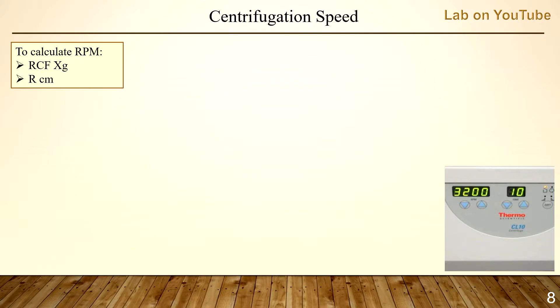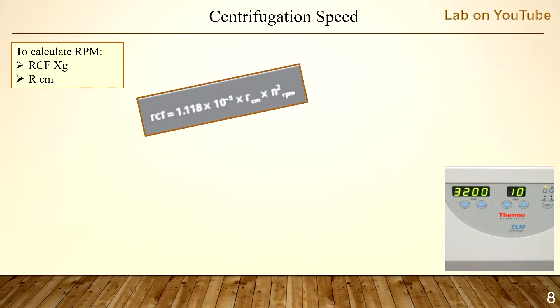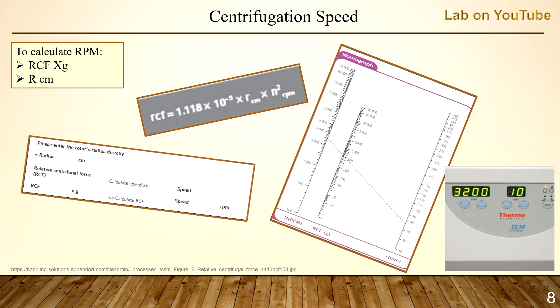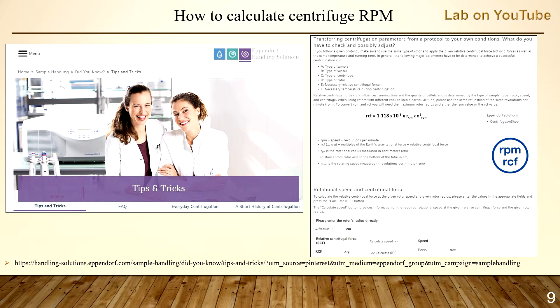After obtaining the RCF and radius, it's time to calculate the RPM. There are three ways: number one, using a formula; number two, a chart or nomograph; and number three, a speed calculator. There is a useful website I recommend — it covers almost all aspects related to centrifuges, including the formula and speed calculator. I'll put the link below this video.